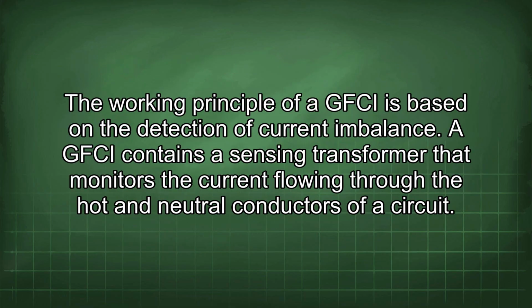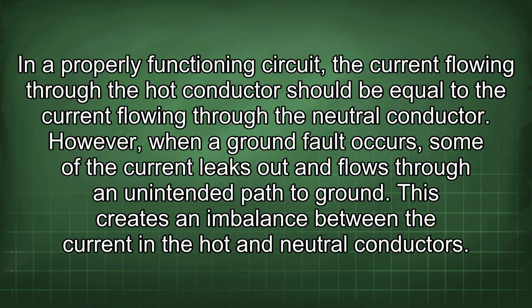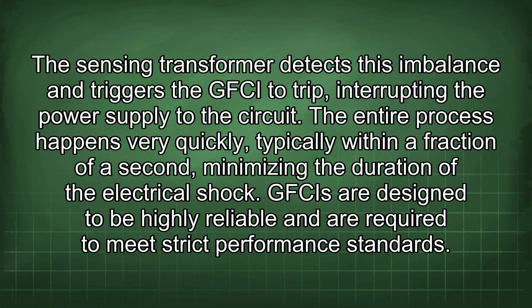The working principle of a GFCI is based on the detection of current imbalance. A GFCI contains a sensing transformer that monitors the current flow through the hot and neutral conductors of a circuit. In a properly functioning circuit, the current flowing through the hot conductor should be equal to the current flowing through the neutral conductor. However, when a ground fault occurs, some of the current leaks out and flows through an unintended path to ground. This creates an imbalance between the current in the hot and neutral conductors. The sensing transformer detects this imbalance and triggers the GFCI to trip, interrupting the power supply to the circuit.